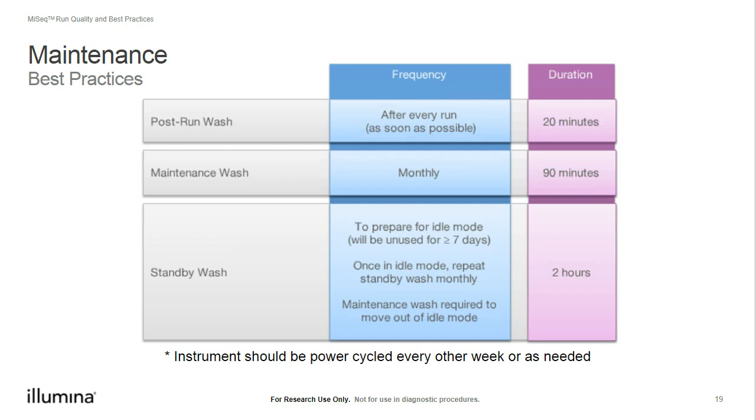It is possible to skip this wash for a period. However, if it's not performed, the instrument will eventually prevent a user from sequencing until the maintenance wash has been completed.